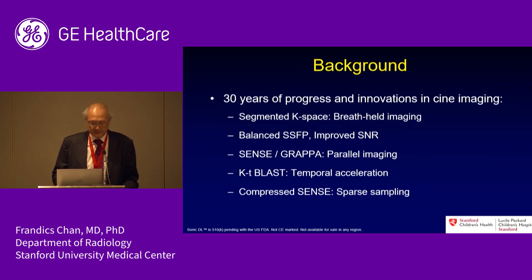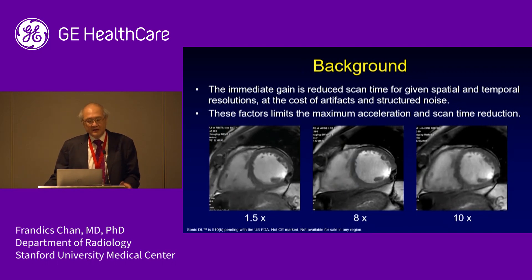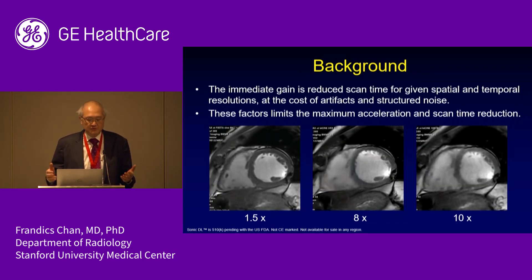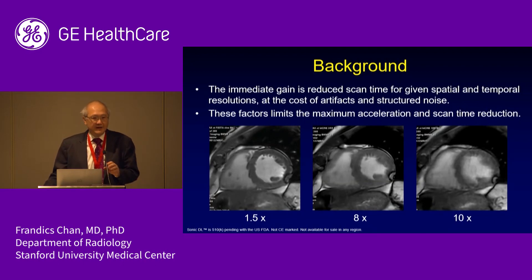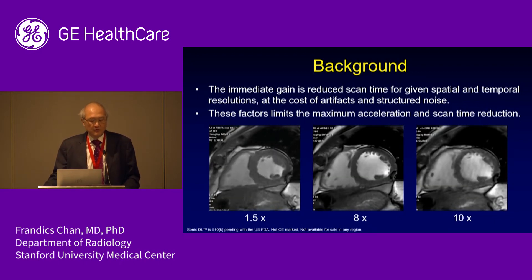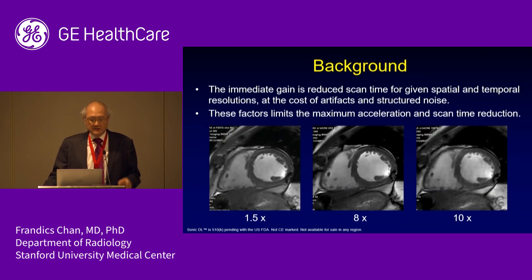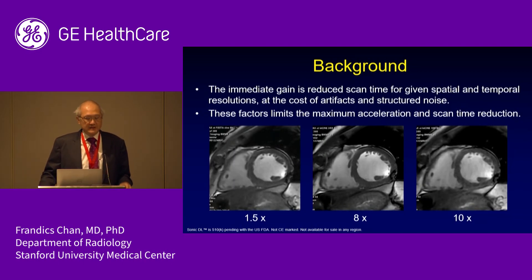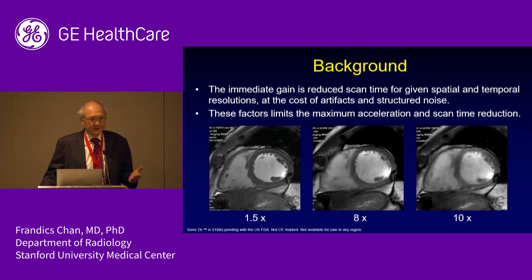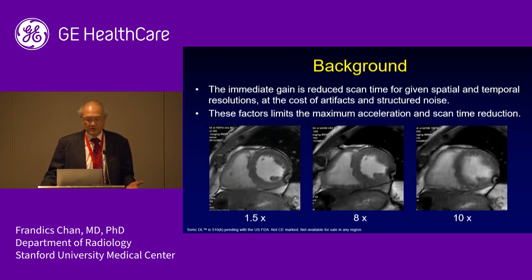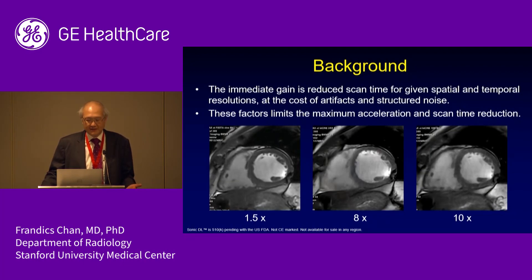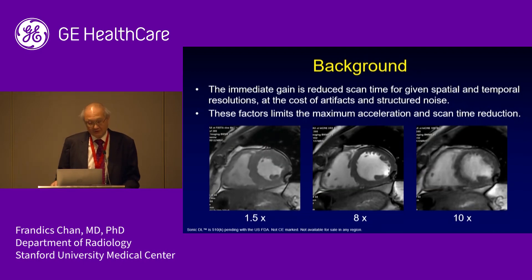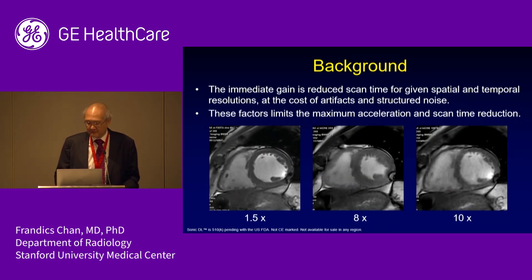We have the highest accelerations possible. The immediate gains of all these technologies is to reduce the scan time for a given spatial and temporal resolution, usually at the cost of artifacts and structured noise. These artifacts limit the maximum acceleration potential — even though theoretically you could do better, when you look at highly accelerated pictures from a clinical point of view, you ask: do I really trust this? That is the fundamental limitation.